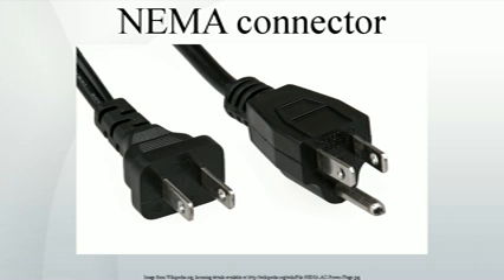The locking coupling makes for a more reliable connection in commercial and industrial settings, where vibration or incidental impact could disconnect a non-locking connector. Locking connectors come in a variety of standardized configurations that follow the same general naming scheme, except that the designations include an L for locking. Locking connectors are designed so that different voltages and current ratings cannot be accidentally intermated. Many specific types exist. Only a few are listed below. Other types include special-purpose connectors for boats, 400 Hz circuits such as used for aircraft, and direct current applications.